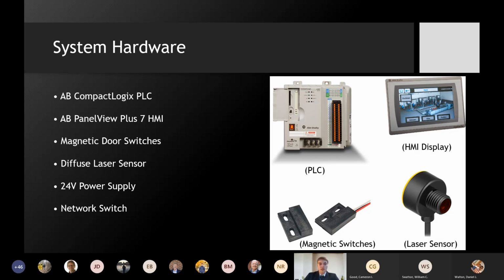Our new hardware additions include an Allen Bradley CompactLogix PLC, an Allen Bradley PanelView Plus 7 HMI display, two magnetic actuating door switches, one diffuse laser sensor, a 24-volt power supply to power all of the above components, and a network switch allowing communication between the PLC, HMI, FANUC robot, and a laptop for programming purposes.